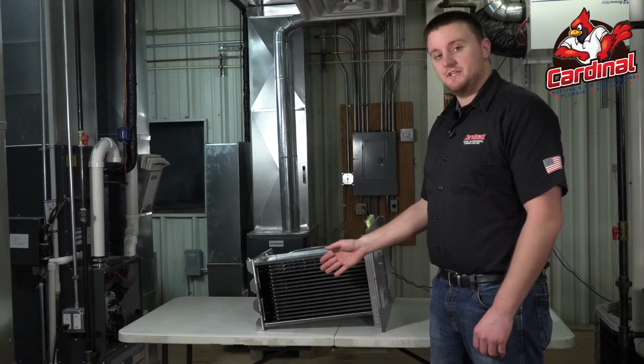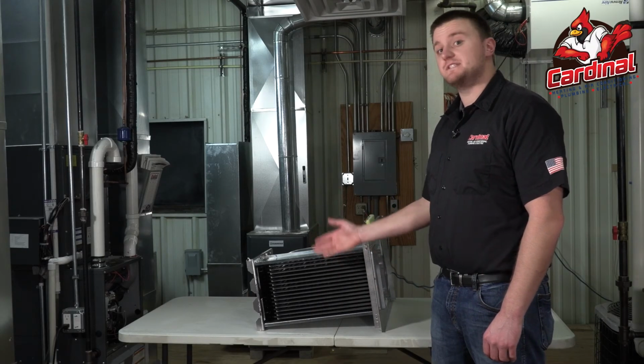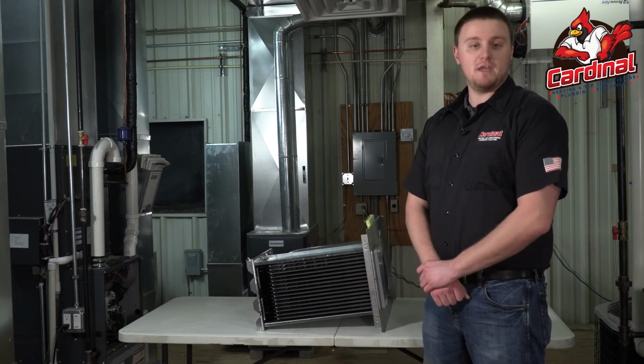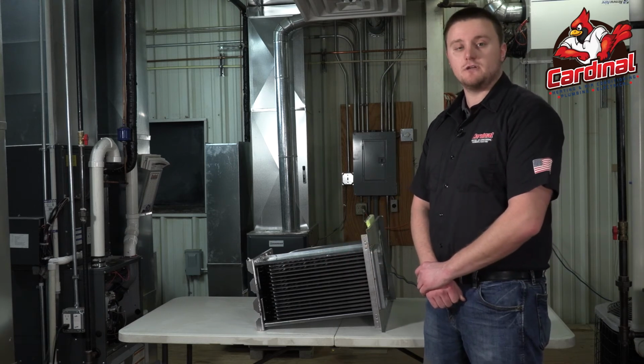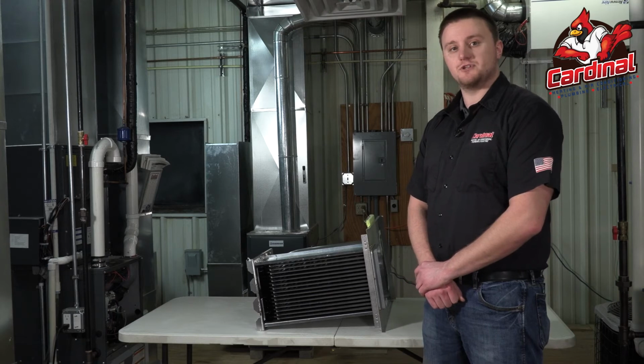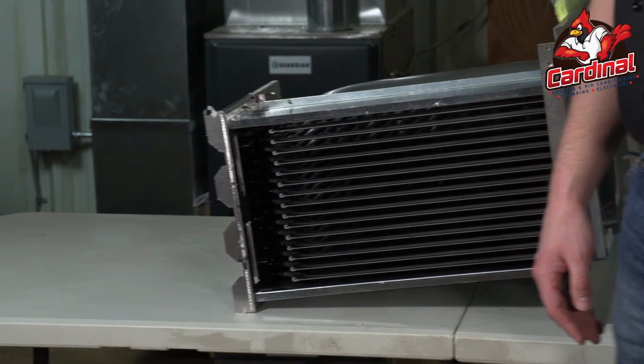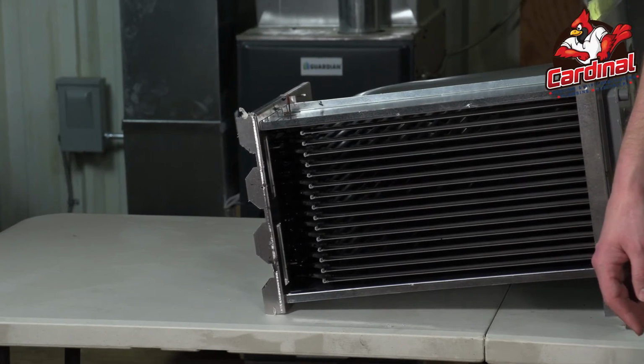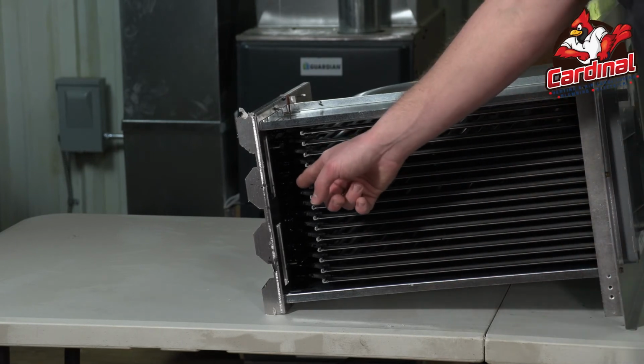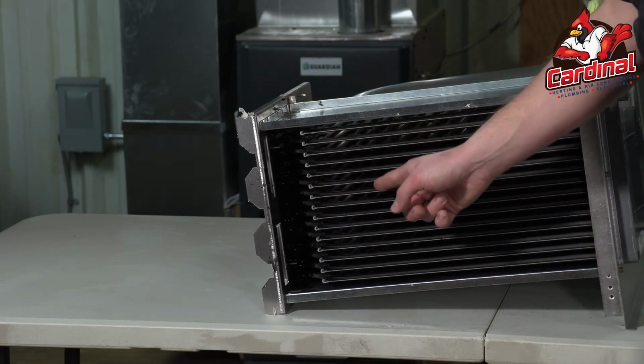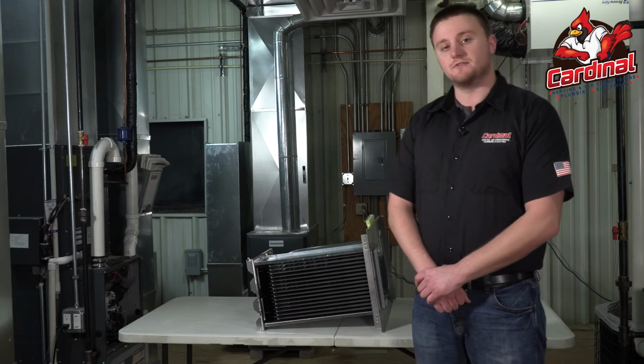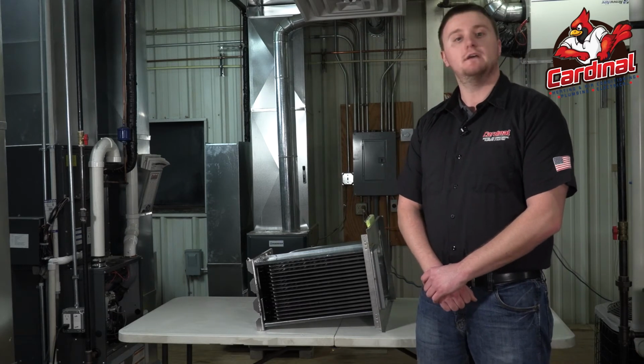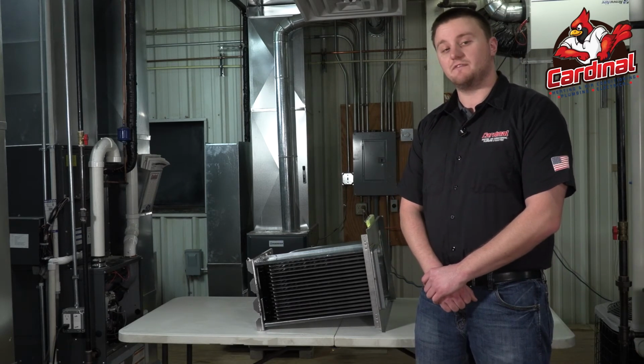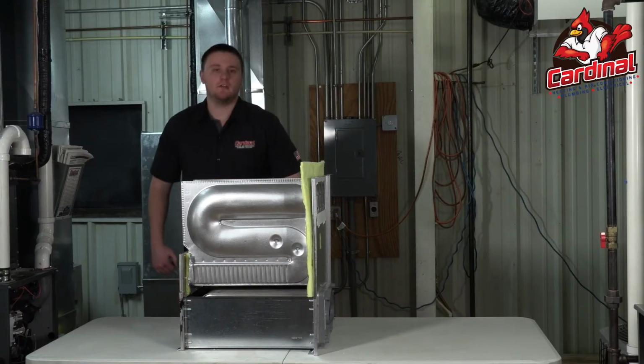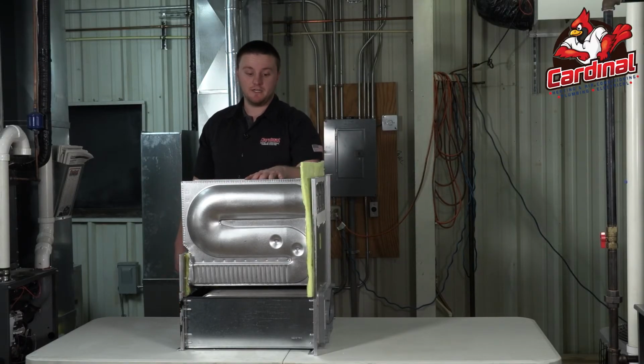Down here is the bottom of the heat exchanger where we find the secondary heat exchanger. The main purpose of the secondary heat exchanger is to gather excessive moisture from condensation. If the water clogs inside the secondary heat exchanger, we're going to look down here for any sort of breach, crack, or hole. If water breaches through that secondary heat exchanger, it is considered a failure and we do have to shut the furnace down. Now that you've gotten a few looks at a good heat exchanger, let's take a look at some failed ones. Follow me.